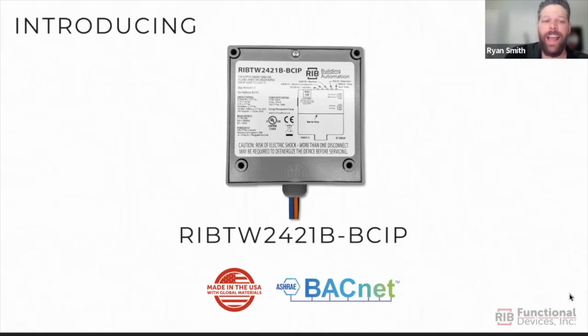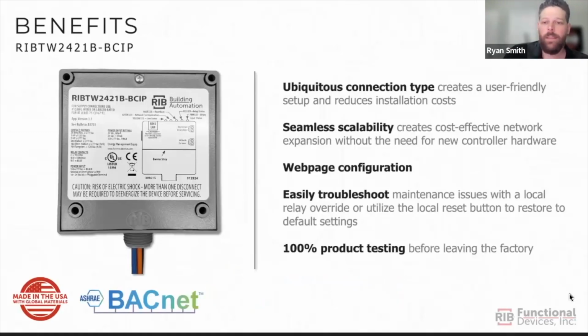This is our new BACnet IP relay, the RIB TW2421B-BC IP. If you're familiar with our BACnet MSTP relay, this is a very similar product with some additional new benefits. This BACnet relay supports IP connections, so adding this to a new or existing network is easier than ever, which can reduce installation costs by not having to run long lengths of new cabling. The BACnet IP relay also saves time and money by not having to add expensive I/O modules to a control panel for additional inputs or outputs. It's configured via a web page, which Henry will get into in later slides.